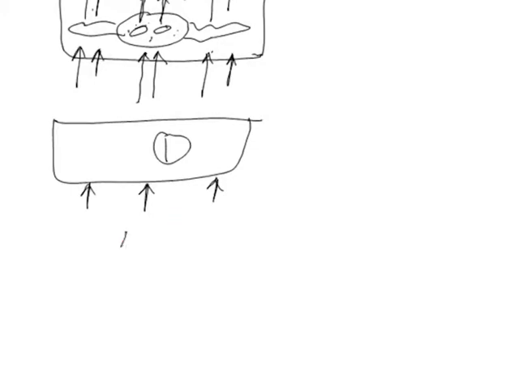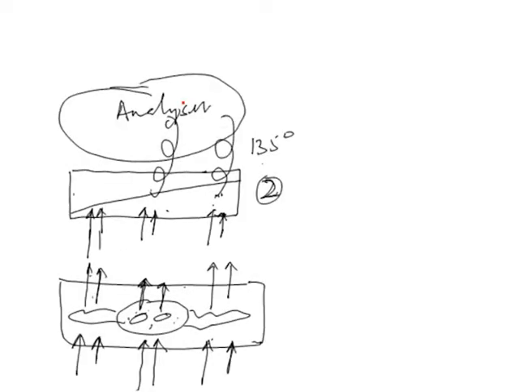As the sheared rays move through the condenser and specimen, they are spatially displaced and not allowed to interfere. The shear distance is around 0.2 micrometers or less; as you decrease the shear distance you increase the resolution. Once they pass through the specimen, there is differential retardation due to thickness and refractive index. This light is then combined by prism number two into elliptically polarized light at 135 degrees.